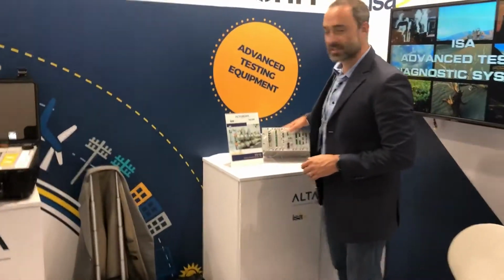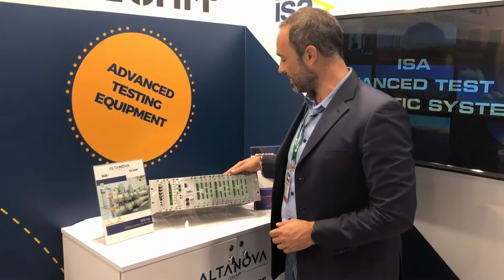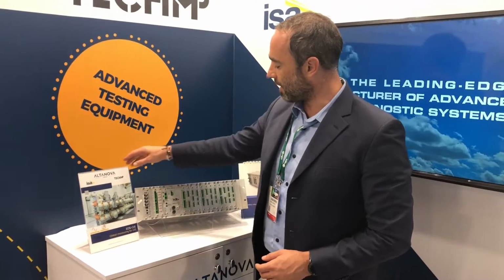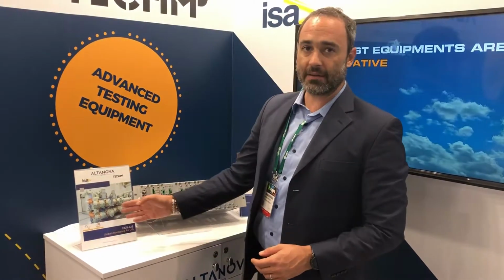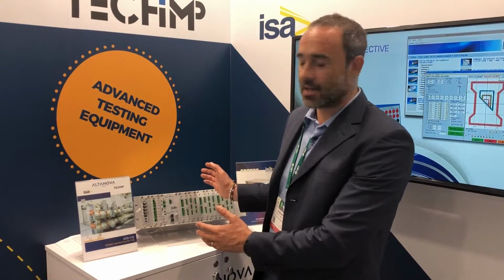Now, since ISA and Techimp have merged in ALTANOVA, some new products have been developed. One of them is the online monitoring system, the global monitoring system, which you can see here, EDS. And with this device, we have already made some very big projects in Q8, so we have been monitoring one GIS and many parameters on that GIS. With this, you can monitor PD. You can also monitor circuit breaker parameters like opening and closing time, flow of the current on the coil, feeder current, etc. But also the parameters of the motor or the battery, which is used to power that motor. Of course, SF6 is another parameter which can be monitored, and the client decides for himself what will be monitored with a system like this. So global monitoring system which can be used basically on any asset.